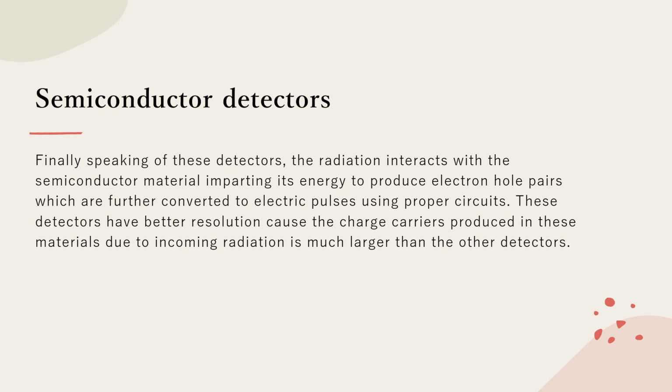So now you guys can ask me about visible light and other photon beams. These beams also interact with the semiconductor detectors to produce electron-hole pairs, thus changing the conductivity and resistance, and can be detected. And neutron beams interact with the material to produce charged particles or gamma rays, and further, these gamma rays or charged particle radiation can be detected from the same principle that I have explained.